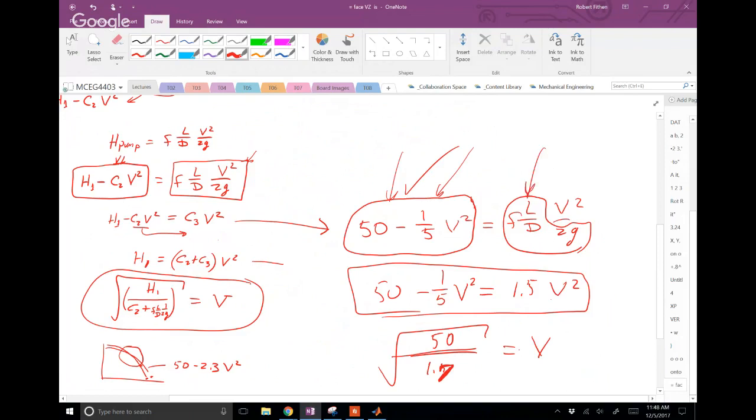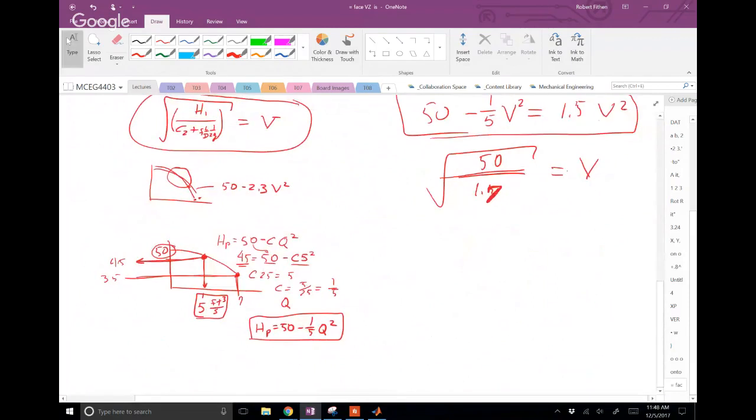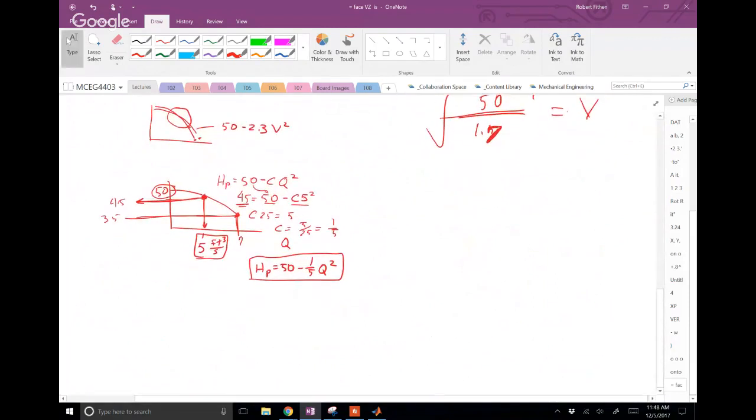Yeah. Now, as far as like picking our second point on that curve, do we just grab anywhere? Well, what I do was, we go down to find like, here's the Q that we're looking, if we know the Q, right? Yeah, see here, that's what I was saying. I was saying when you're looking at a real pump curve and you're like, well, if I pick a point right here, it's going to be really touchy. So I got to move out here somewhere reasonable.